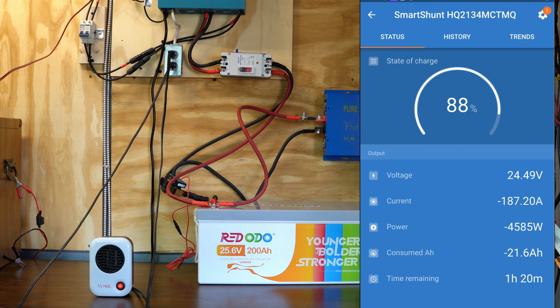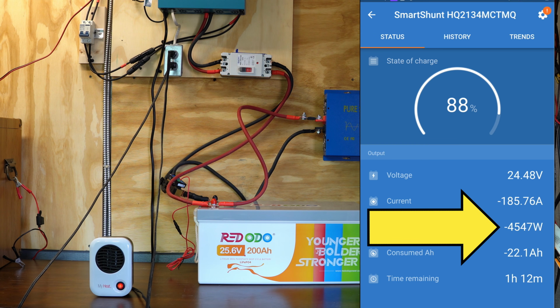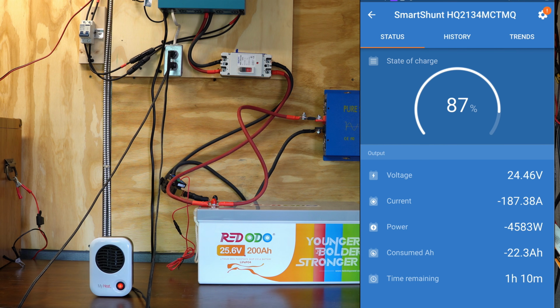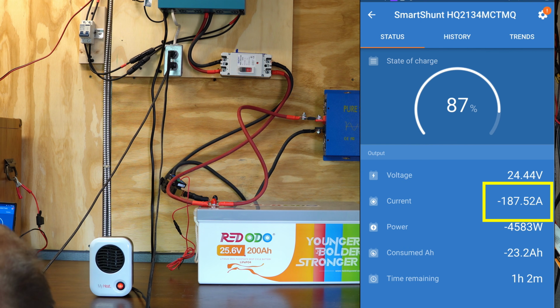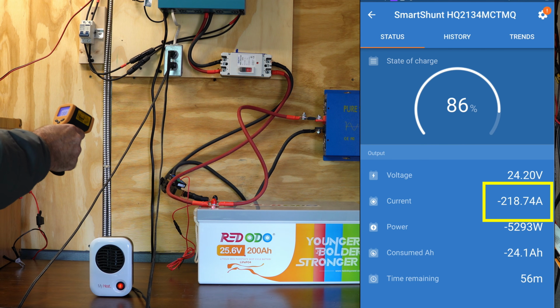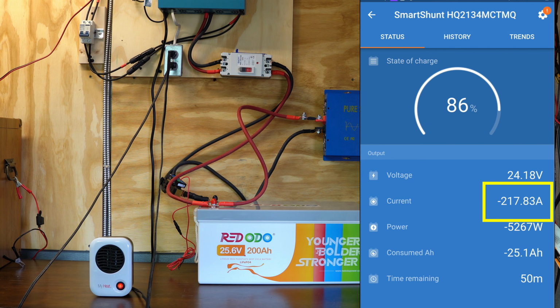Currently pulling a combined 4500 watts. All right, I'm going to push that 3000 watt unit a little further. I've got one more load on my oil heater, and we shall see how it reacts. This is going to push it over 3000, and it should also give us in excess of 200 amps, so keep your eye on the current parameter there. 186 amps currently — this is going to push us over. So we are at 218 amps. That 200 amp BMS is giving us a little bit of headroom here. Let me check the temperature — 68 degrees Fahrenheit on the terminals.